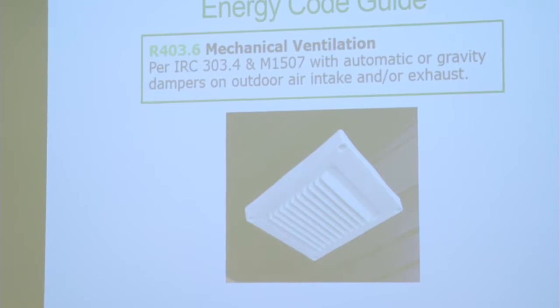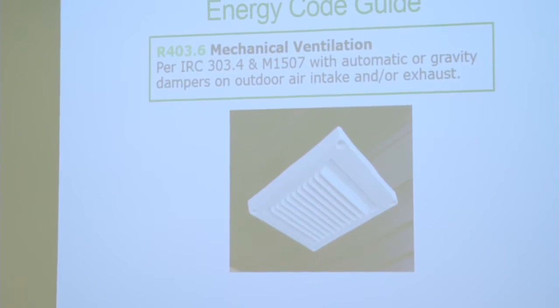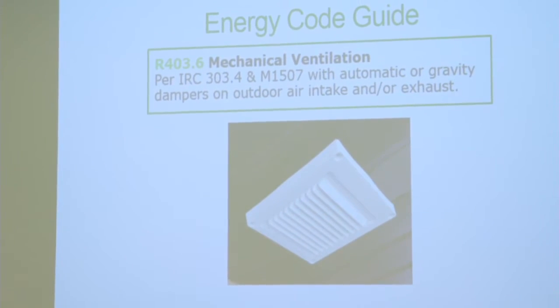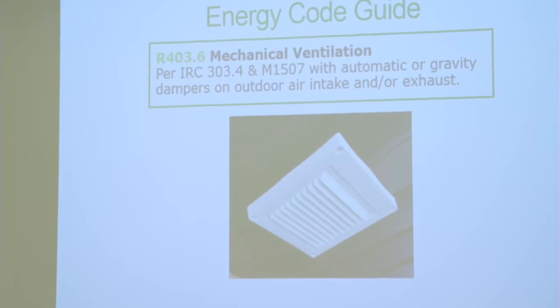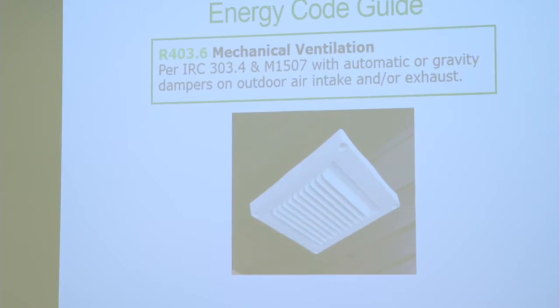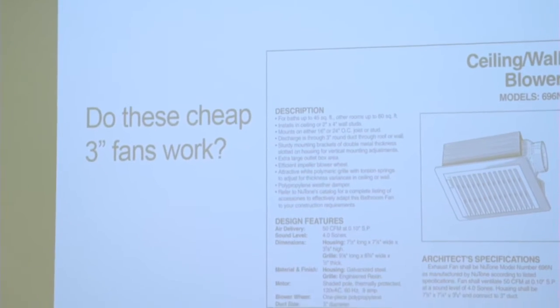If you're venting bath fans out of the soffit, they have to have a backdraft damper in it. And I saw a whole bunch of these one day when I was doing inspections, and they're just little cheapies without a backdraft damper. So look up in there and make sure it has a backdraft damper.